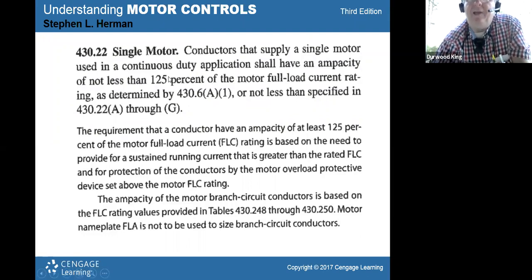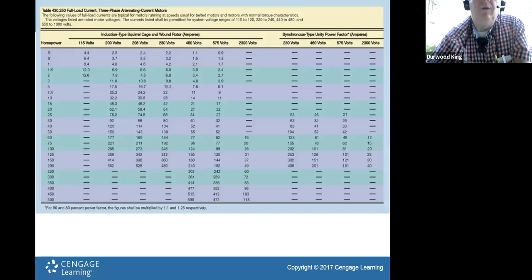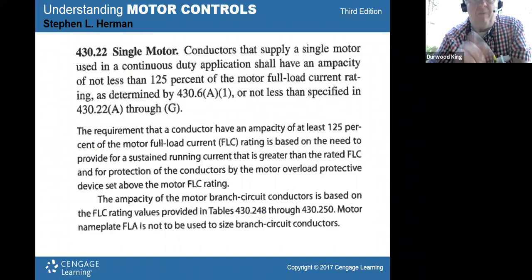If you read right here out of the code book, it says that conductors or wires that supply a single motor, if it's continuous duty, shall have an ampacity, which is amp rating, not less than 125% of full load current rating, determined by these articles in the code book. And all of that actually comes from that chart with the amp ratings that we just looked at. You multiply that chart number by 1.25, and then you go pick a wire size.